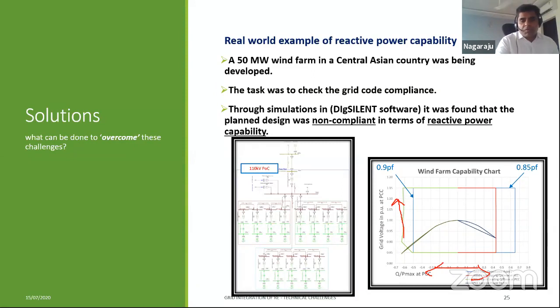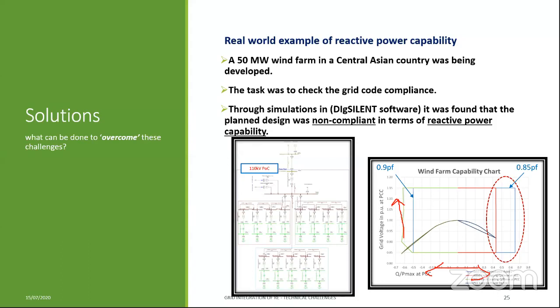What was happening is that with the current design, it was unable to meet the requirement. This was the lagging part. On the leading side, there was a shortage of nearly 12 MVAR. So how do we handle this? We consider all the scenarios, do the load flow simulations, measure the reactive power export at the point of connection, and plot that against the requirement to find out the gap. That gap has to be filled with some other form of support.